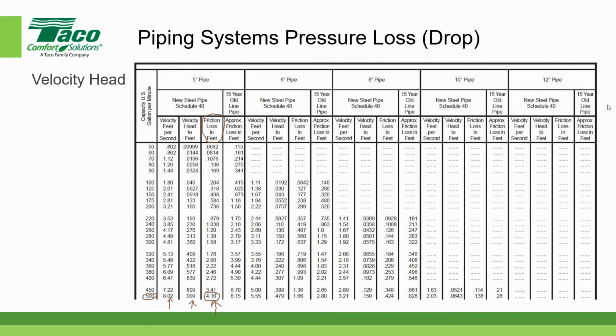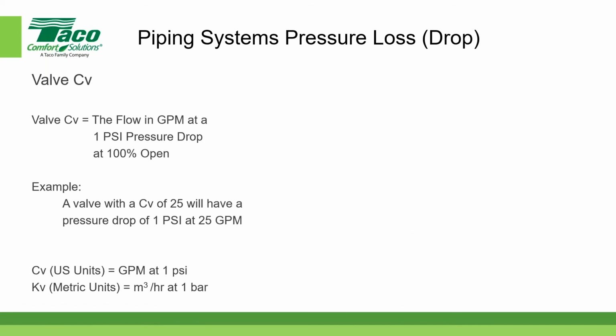If a valve has a CV of 35, what is the pressure drop at 17 GPM? That's a good question. Let's see if I can go to the screen where we were a moment ago. So there's the CV. And what was the value, Brett, that they had? Half of it, 17.5. Okay, so what you have to do is use this equation that says the pressure, we'll call it the head, at the new flow is equal to the initial pressure times the ratio of the flow squared.